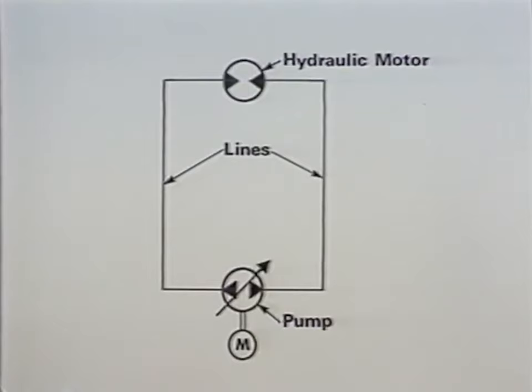A closed circuit consists of a pump and a hydraulic motor that are interconnected with each other via lines. The pump has a variable displacement while the hydraulic motor has a fixed displacement. An electric motor powers the pump.